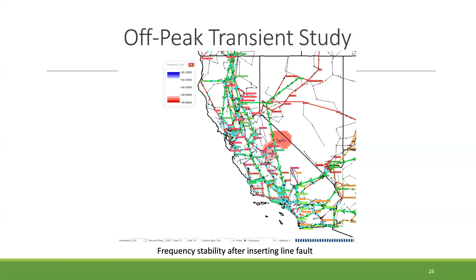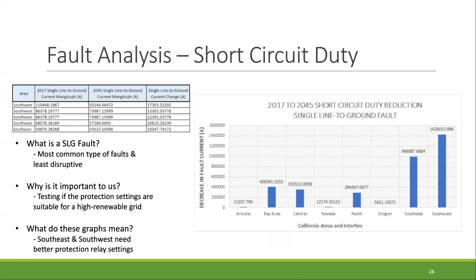The team looked at the short circuit duty impacts as a result of the 2045 goal. If the short circuit duty is reduced significantly, it will have a major impact on the protection and the IBR settings. Here is a comparison of the single line to ground fault duty for the years 2017 to 2045. To the right, you can see that the southeast and southwest have the most reduction in these areas.